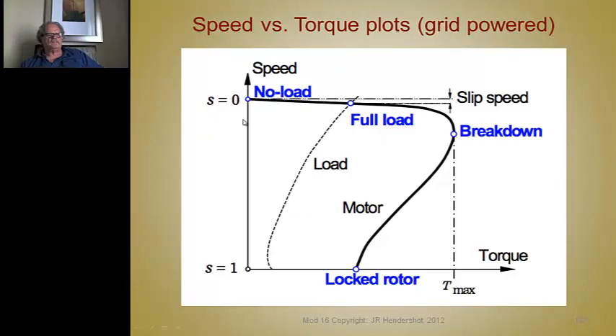So many motors aren't loaded down till they're already up to full speed. But still, the motor is going to go through this same torque speed profile from start, whether it's loaded down to produce that much torque or not doesn't really matter. Now this is a load characteristic of something like a fan. A compressor would be different, but this is like a fan blade. So the starting torque of a fan blade is very low. You've got a little friction to overcome, but it's mostly all inertia, and it really starts under no load. So it's no problem to use an induction motor to start a fan load like that.